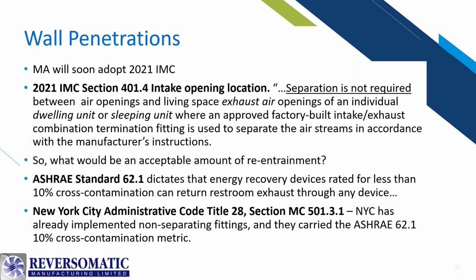Well, our idea so far, and to be fair, it hasn't been adopted yet, is that ASHRAE standard 62.1 should have a say here, where it dictates that energy recovery devices rated for less than 10% cross-contamination can return restroom exhaust through any device. So basically, as long as you're not re-entraining 10% cross-contamination, then it should be fine. And actually, New York City has already adopted the 2021 IMC, and they've given this interpretation some validity in their administrative code, Title 28, Section MC 501.3.1, where they have already carried over that 10% cross-contamination metric.